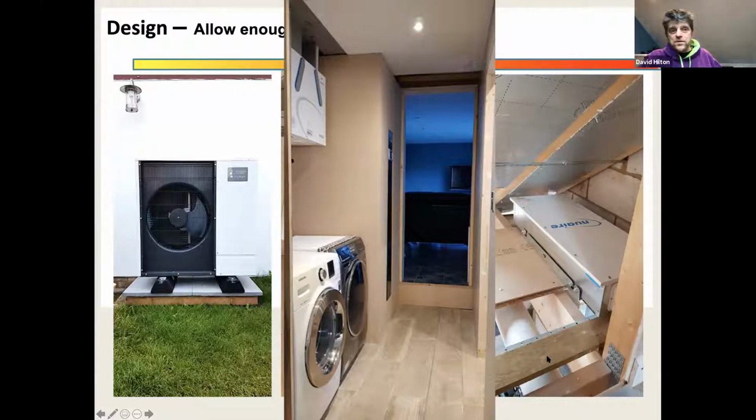But if you've got an existing property, then you don't always have that benefit. And we used 3 or 4 different types of ducts to be able to move around in the property just to get it right. And because the house wasn't airtight, we've actually put 2 terminals in each room, one bringing air in, one bringing it out. So we've balanced each room to not have air leakage, rather than balancing the whole house. That way we do not have to have undercuts under the doors, and the whole house will ventilate and just be fresh.